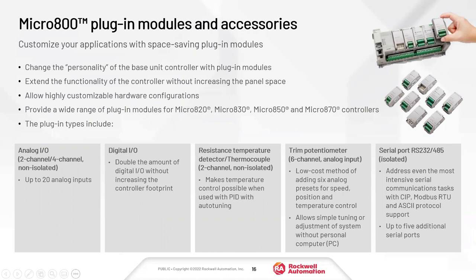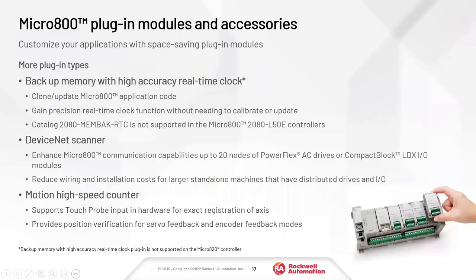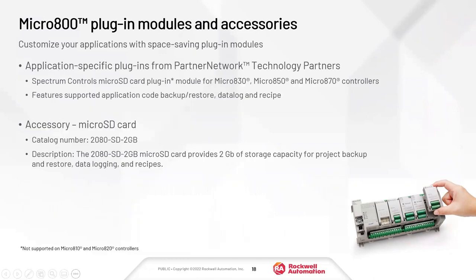Plugin module options include analog IO in 2 and 4 channel versions for 4-20mA signals, digital IO, RTD, thermocouple, and even a trim pot card with six little trim pots built right in — so you can make adjustments with a screwdriver without a laptop. There's a serial port plugin that also supports CIP, Modbus RTU, and ASCII. There's a real-time clock backup memory plugin mainly for the 850 and 870, a DeviceNet scanner, and high-speed counter. Specialty cards are also available from partner Spectrum Controls.